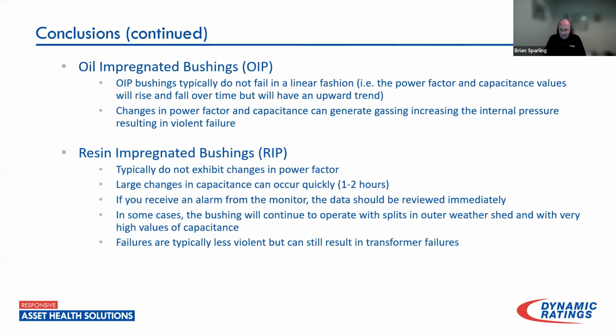So when you receive an alarm from the monitor, review the data immediately. In some cases, the bushing will continue to operate with splits in the outer weather shed and with very high values of capacitance. And failures are typically less violent, but can still result in transformer failures. Regarding the bushing failure that we caught the first time, the utility that owned that transformer has a mix of OIP and RIP bushings in their fleet. They had a procedure for what to do when bushing alarms came in. And this is important: the alarm response procedure for transformers is really something that people often forget about.